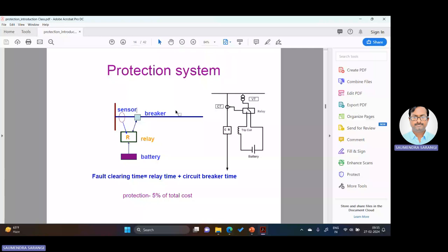And the heat generation, I square R T, is quite high. If you want that your conductor should not burn, then in I square R T, the time T has to be limited. If you have to limit T within milliseconds, like 2 cycles, that is 40 milliseconds, to 0.1 second, that is 5 cycles, then only it is possible to break the circuit during the faulty condition and disconnect the faulty section. So the operation time for a high voltage transmission line is very less.